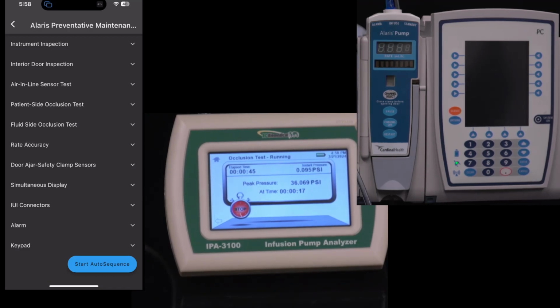Can this be used for other things outside of the IV pumps, such as dialysis machines? If I was to measure 125 ml for 15 minutes? Sure. Measuring 125 milliliters per hour for 15 minutes, yeah, you can set it up for multiple hours of dispenses. No problem at all. We've tested it with really low flow rates, down at 10 milliliters per hour, 5 milliliters per hour, and we've gone up to really high flow rates. So anywhere across the range, it works really well.